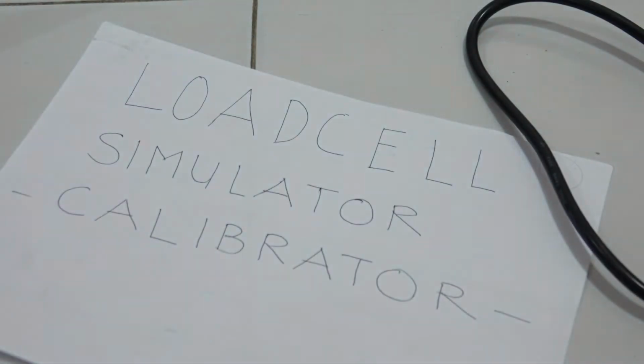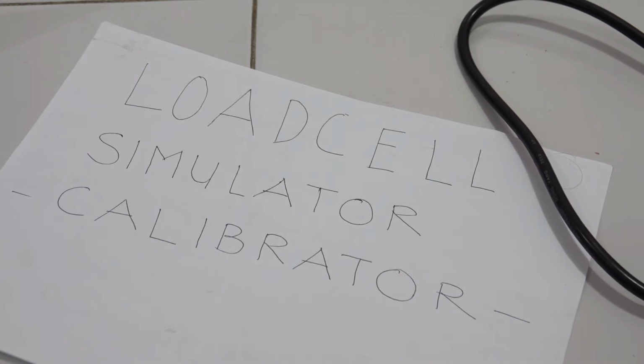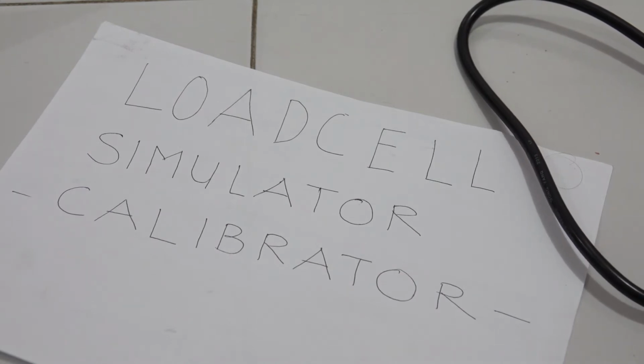Bear in mind also that there is no standard mentioning the colors of the load cell wires. In a load cell there are sometimes 4 wires, 6 wires, and the colors of the wires are not the same across manufacturers. There is no standard at all, so you have to carefully read the user manual of the load cell and the user manual of the load cell indicator. Then you have to match what is the excitation voltage, what is the signal, what is the sensing, and sometimes what is the number for the shield.